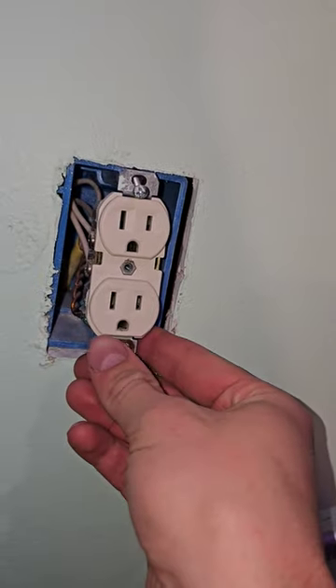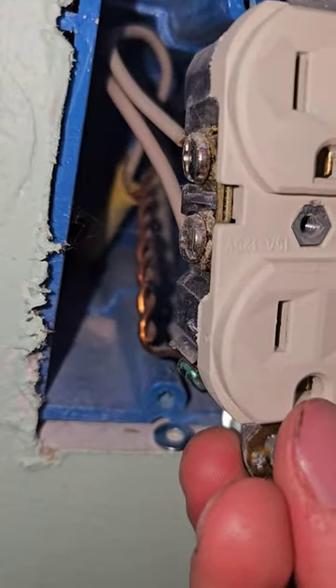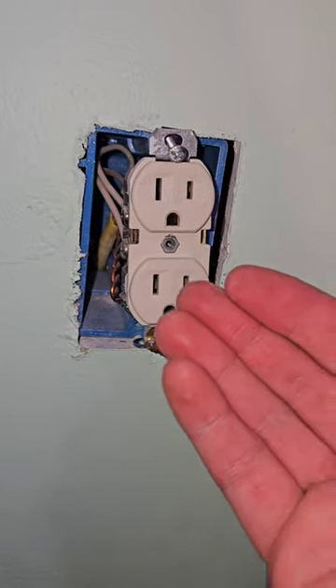I also hate whatever electrician wired this. Look how short that is — the pigtail right there. You can't get it out of the wall any further. Code is six inches.